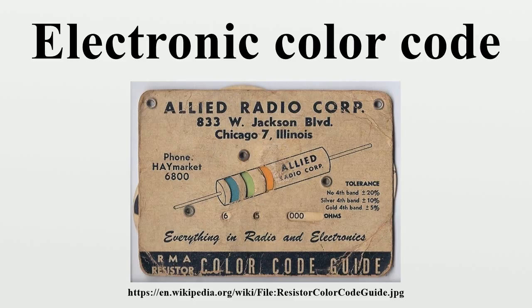Transformer wiring color codes. Power transformers used in North American vacuum tube equipment were often color-coded to identify the leads. Black was the primary connection, red secondary for the B+, red with a yellow tracer was the center tap for the B+ full-wave rectifier winding. Green or brown was the heater voltage for all tubes. Yellow was the filament voltage for the rectifier tube. 2 wires of each color were provided for each circuit, and phasing was not identified by the color code.